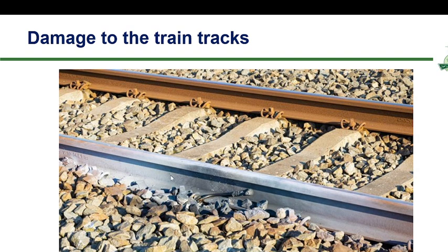You can see here there is some arc, and such incidents can lead not only to power system failures but also to significant disruptions in transportation networks, transforming into safety risk and requiring costly repairs. And in addition, this example underlines the importance of maintaining proper clearance distances, continuous monitoring of line conditions, and ensuring that protection systems operate correctly to prevent such cascading impacts on critical infrastructures.